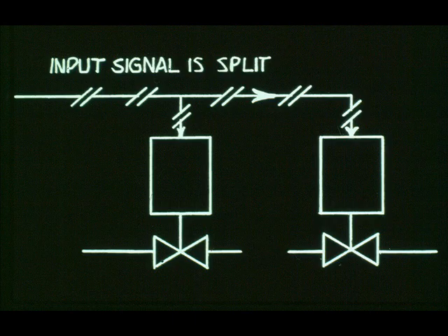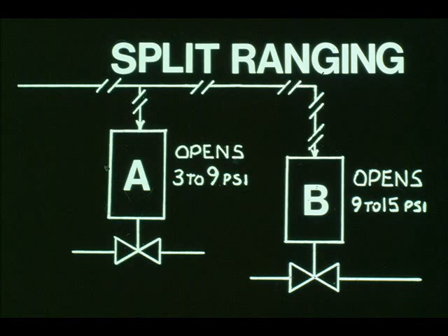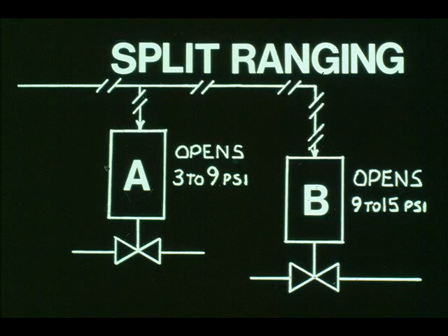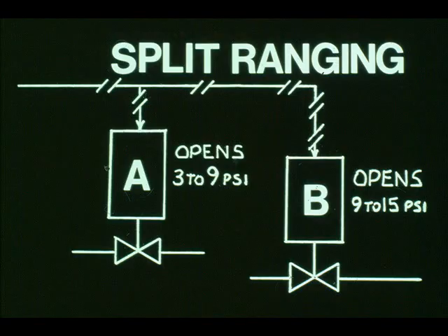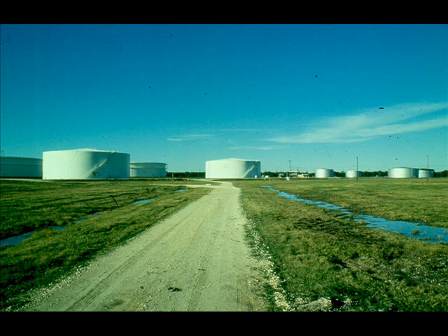Piston operators can be split ranged. The term split ranged means dividing the input signal between two or more control valves. For example, Valve A will open from 3 to 9 PSI, and Valve B will open from 9 to 15 PSI. This dual valve installation — one small valve and one large valve — permits great rangeability. A disadvantage in using a piston operator is the need for a source of air supply, which can become a problem in remote locations.